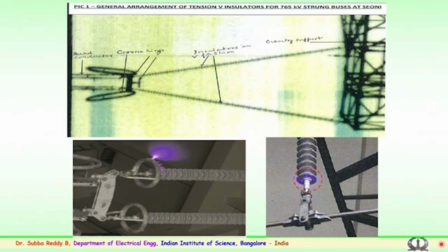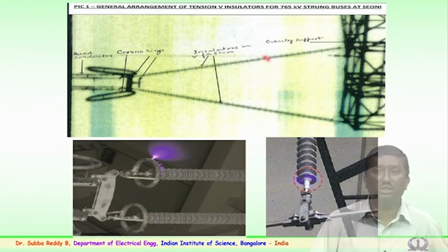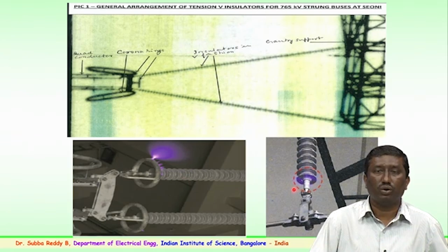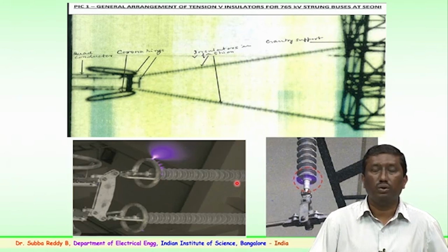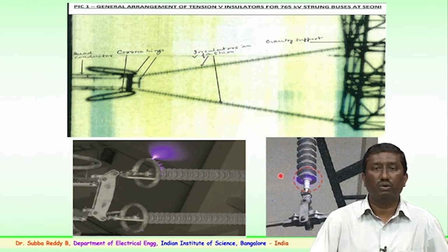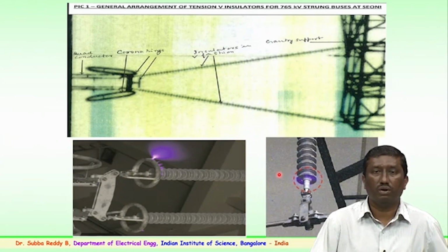So, how is corona important, and why does it degrade the surface? As you see here, the corona comes from the hardware, here from the corona control rings. This corona which is generated, the discharges which are continuous, is likely to damage the sheds, continuously impinging on the surface of the insulator. Over a period of time, the surface of the polymer insulator, which is supposed to be hydrophobic, loses its properties, and the surface degrades and could lead to the failure of the insulation.